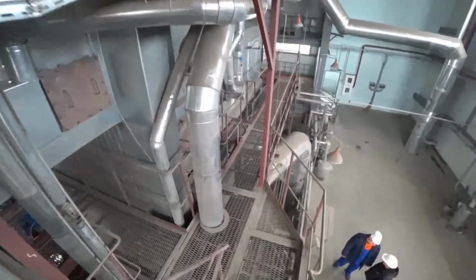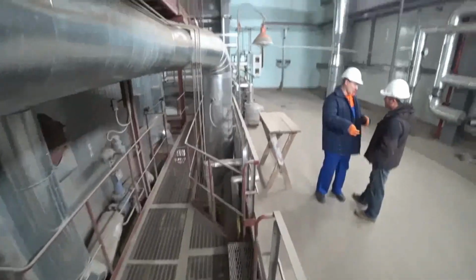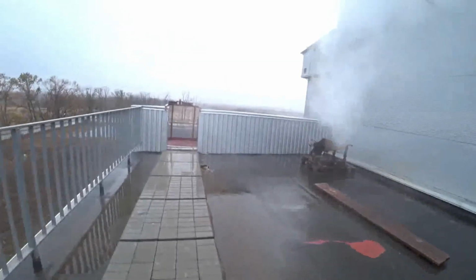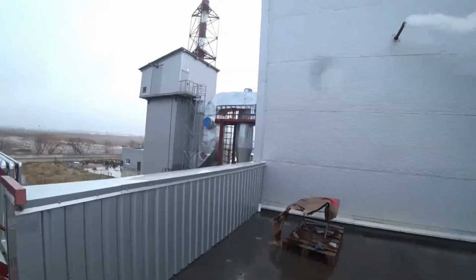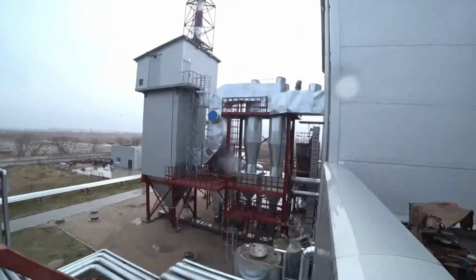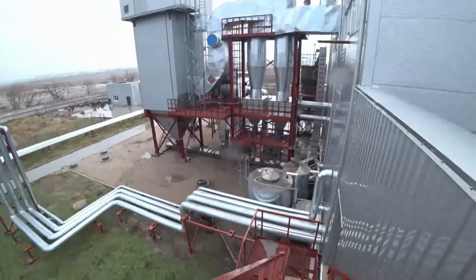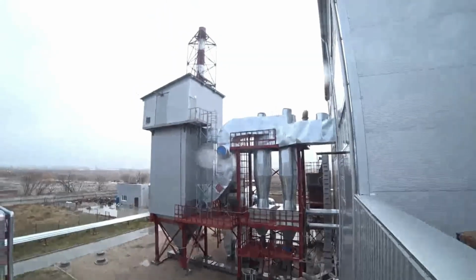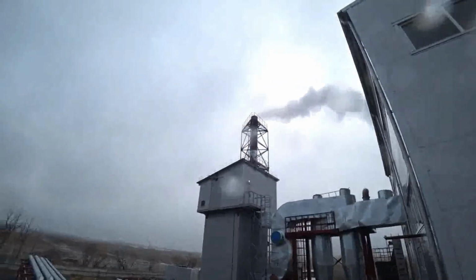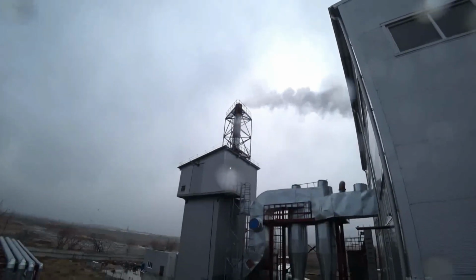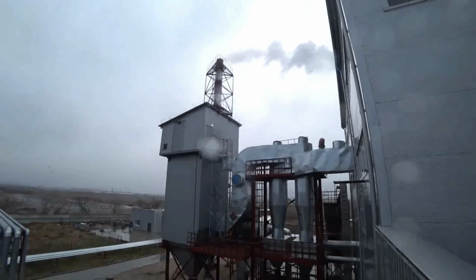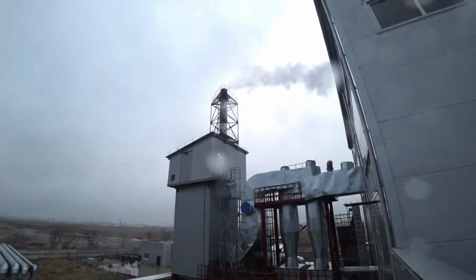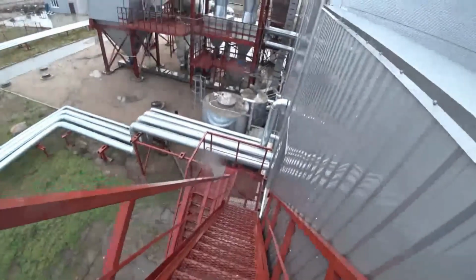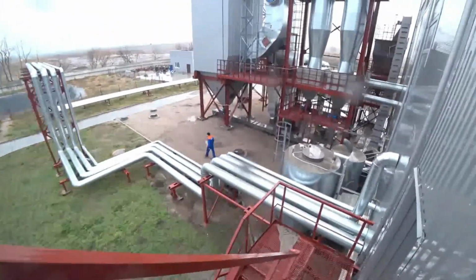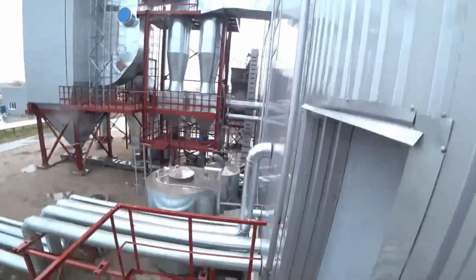Next, we go down, and I will take you to the ash removal and flue gas cleaning system. Our path will pass through the roof of the administrative and household building. The flue gas cleaning system is implemented in 2 stages. The first stage is steam dust cyclones. The second is a bag filter. The operating temperature of the bag filter is 200 degrees. The maximum is 240. The peak short-term temperature is 260 degrees. We go down the stairs and see the steam and hot water pipelines that go to the poultry farm.